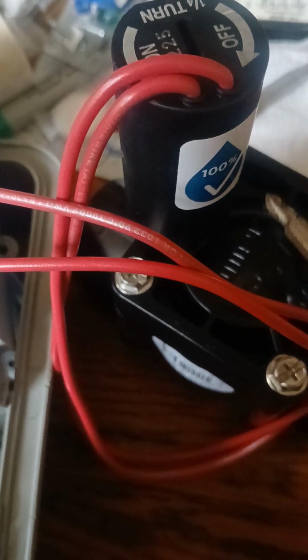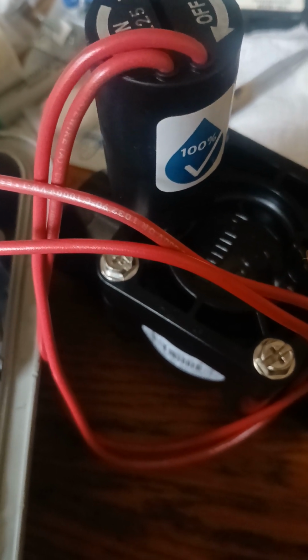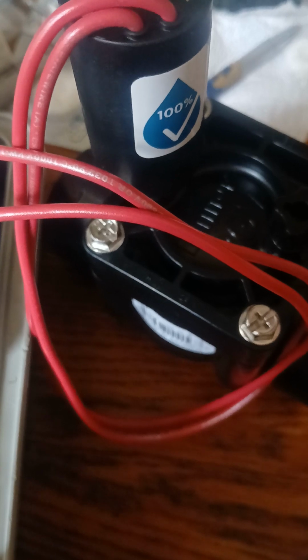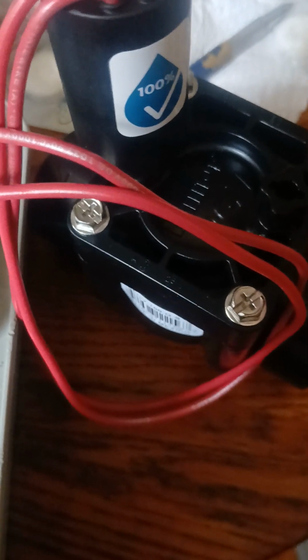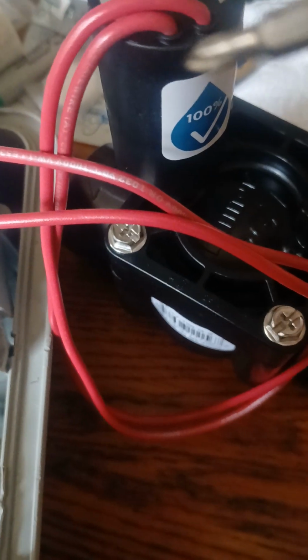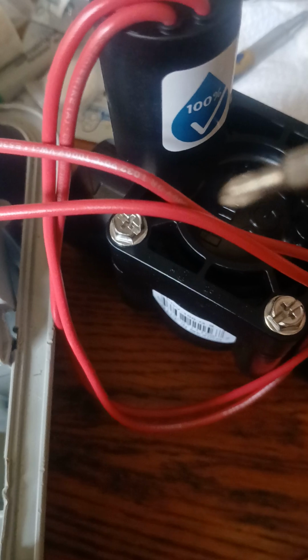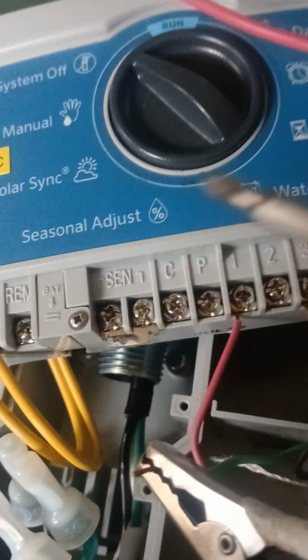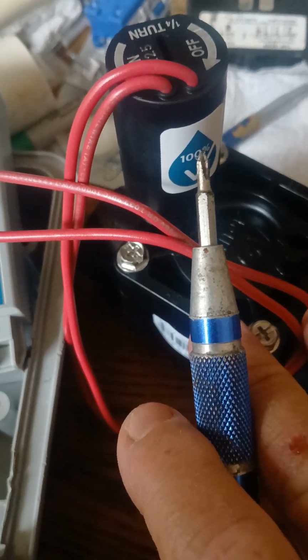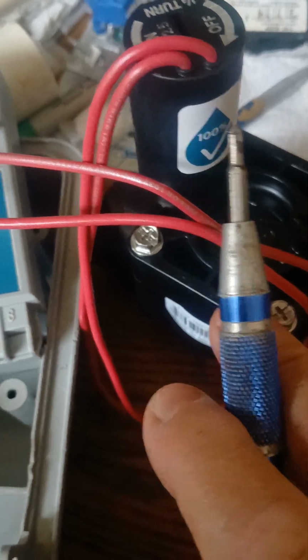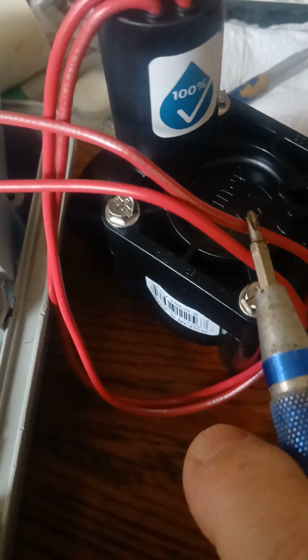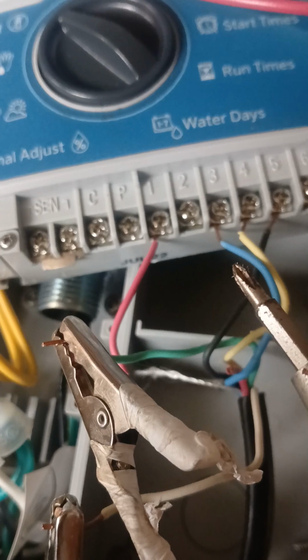At least the solenoid on this valve may test good for a lawn sprinkler system, a valve for irrigation or lawn irrigation. So we're ohming the valve out, perhaps the solenoid on the valve, to test to see if it's good via the control box here, using a multimeter, and we've got the valve here. This valve would be buried somewhere in a box, perhaps out in the yard. So that is the way to test the irrigation control valve solenoid from the controller of the sprinkler system, using a multimeter.